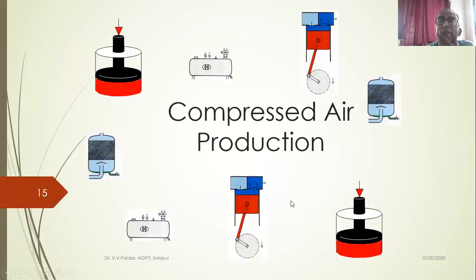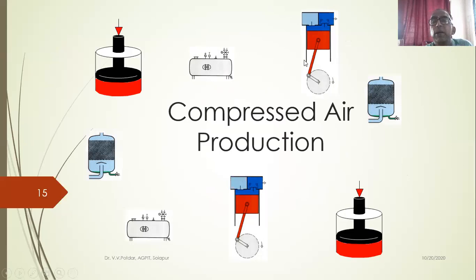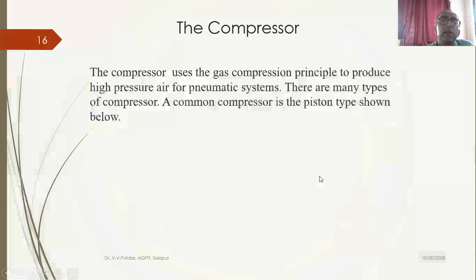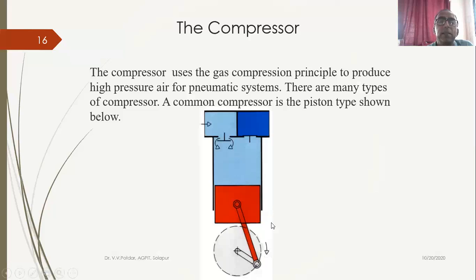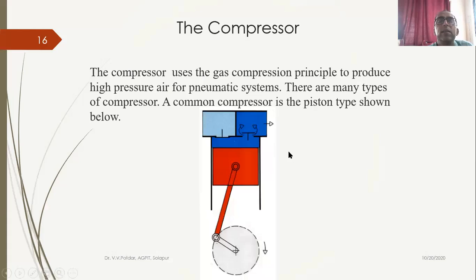For compressed air production, as seen in the first slide, the air receiver has a pressure gauge, a temperature gauge, and a safety relief valve to safeguard the pressure vessel. There is a valve for taking compressed air to the application, and a drain for removing trapped water or for maintenance. The compressor — reciprocating type — has a filter at inlet. The compressor uses the gas compression principle to produce high-pressure air for the pneumatic system. A common compressor is the piston type.